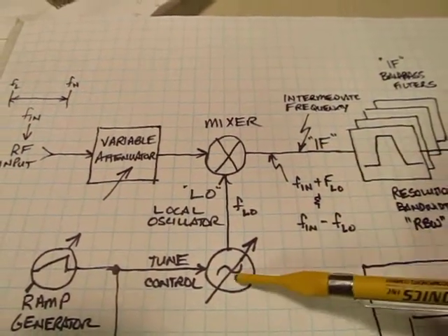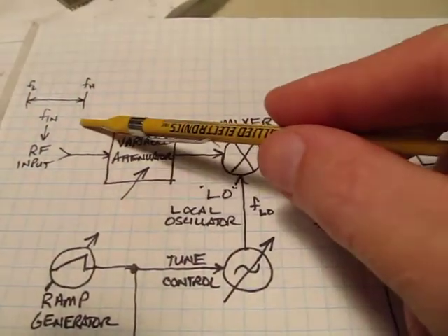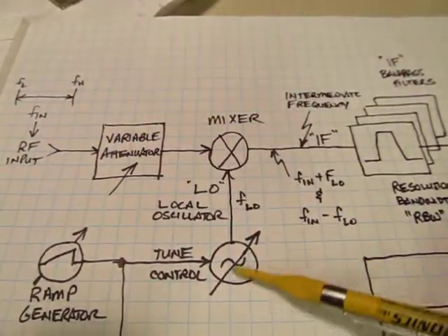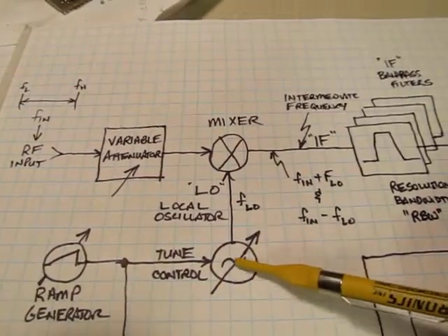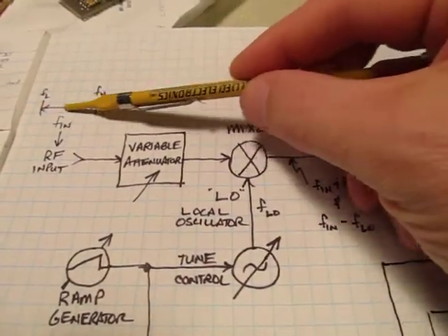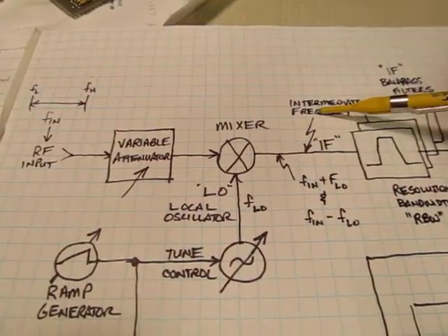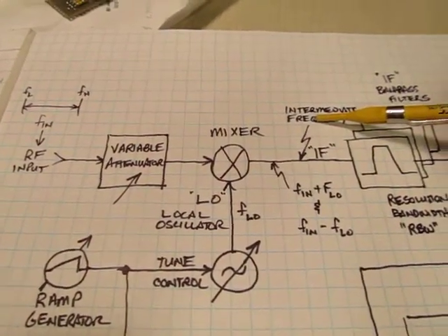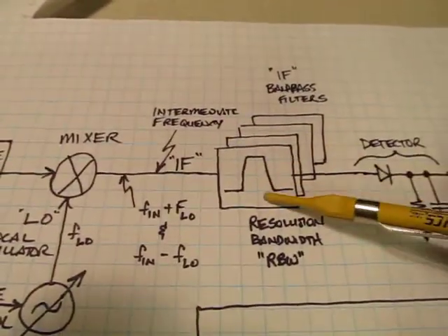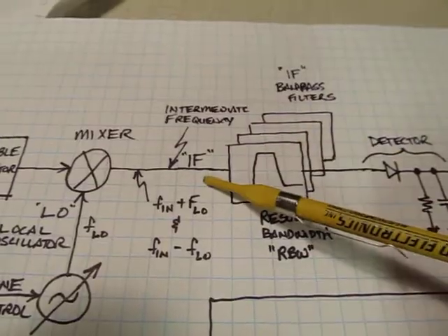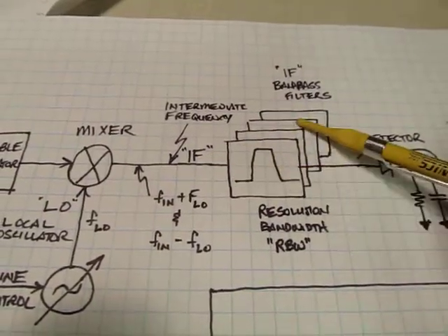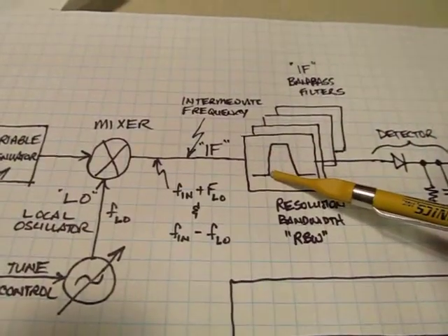And the idea here is that by creating this, what we call intermediate frequency here, we essentially all we have to do to make tunable, to basically tune across a given frequency range, the only thing we have to make tunable is this local oscillator. So basically by selecting a particular local oscillator frequency, as we tune this back and forth, we can take any frequency from this range of f_IN and make it land at a particular desired frequency here that we'll call the intermediate frequency. So the idea is that all of our resolution bandwidth, our filtering that we're going to do, and amplification that we're going to do on the signal is only going to happen at one frequency. So it makes the job, the design of these filters much easier.